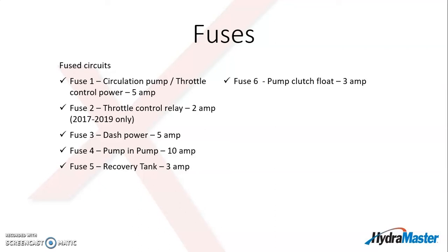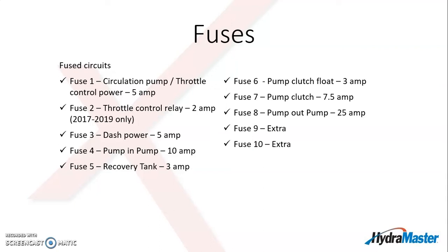Fuse 6 is the 3 amp fuse for the pump clutch float and the pump clutch relay. Fuse 7 is the pump clutch itself. That's a 7.5 amp fuse. So the float switch and the clutch are fused separately. Fuse 8 is a 25 amp fuse for the pump out pump. And fuses 9 and 10 are not used currently, and they have extra fuses plugged into them.